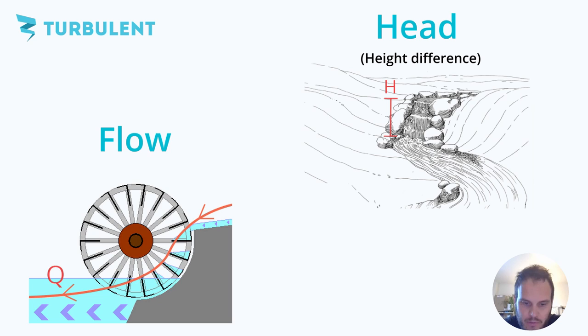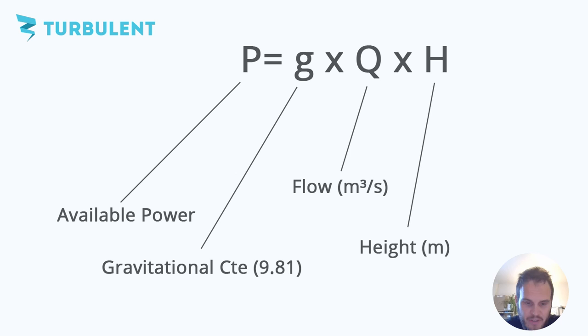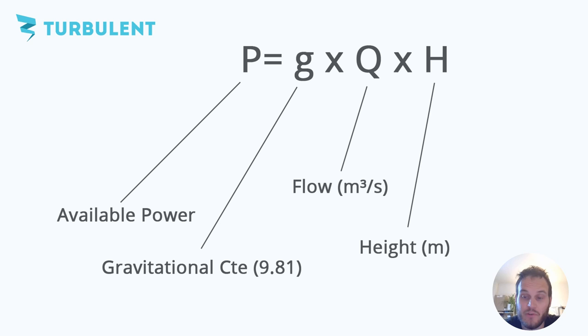For hydropower you need two things to generate power: a certain amount of water or also called flow, and a height for it to fall down from. This height difference is the thing that pushes the water through your turbine basically. So there's a simple formula to calculate the power of a river or a creek and goes like this. The power that's available in your river is equal to the gravitational constant g times the flow in cubic meters per second times the height difference over which the water falls down in meter.